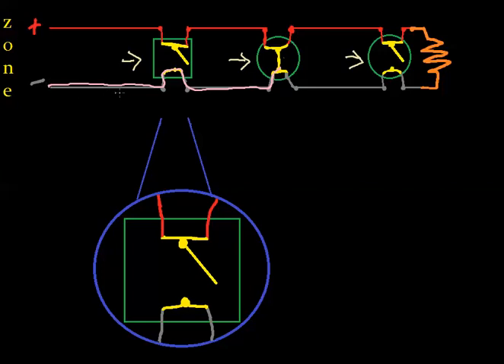this current is trying to get from the negative to the positive. It's flowing through all the electrons in this wire, and it's going to go, actually, that's probably not the right way to say that, but we'll get more into that later. It's going to take the path of least resistance, right? It's going to go in and out of this pull station. It's going to go through this heat detector, back to positive. It's essentially a dead short. Almost none of it's going to go through this resistor.